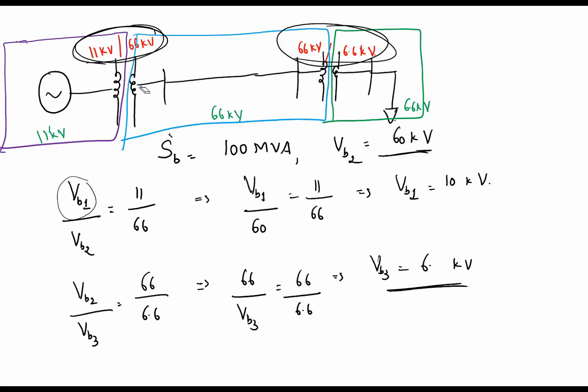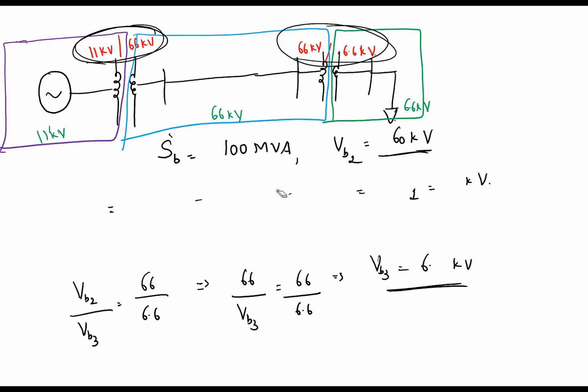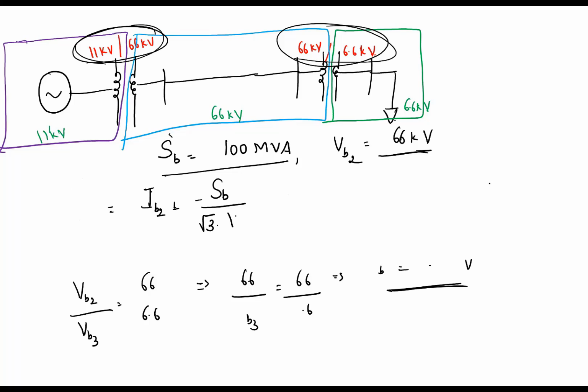Okay. Now this last topic which I want to tell you in this context is, once you know base voltage, you can also calculate base current. So now suppose I know my base MVA is common, that is 100 MVA, and base voltage is known. Now base current in section 2, IB2, will become SB divided by √3 into VB. So 100 divided by √3 into 66. This many kiloampere will be the base current in section 2. Likewise, you can calculate base current in other sections also.